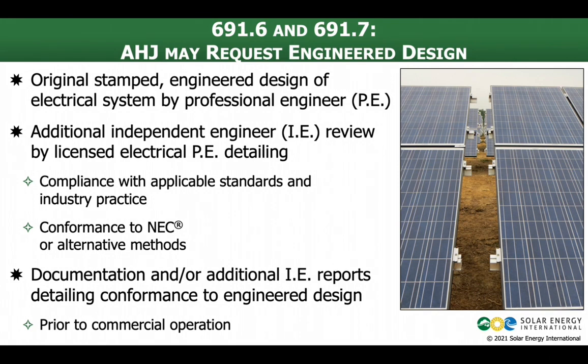We're just talking about the electrical here. An engineered design, an IE looking at that design, verifying it is done correctly, and then an IE verifying that the system was installed correctly. So it's the AHJ's ability to request these that is fundamental to the way 691 works as compared to how normally the National Electrical Code is enforced by the AHJ, where they are doing plan set review, they're doing inspections. This is just an alternative means to make that happen.